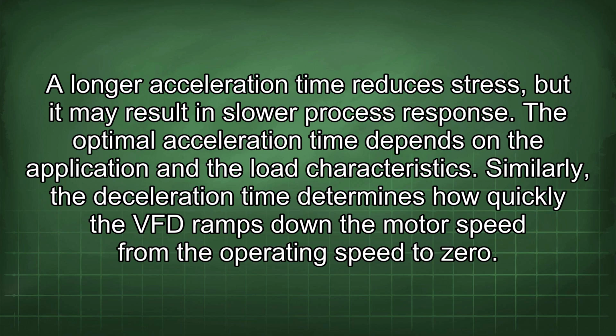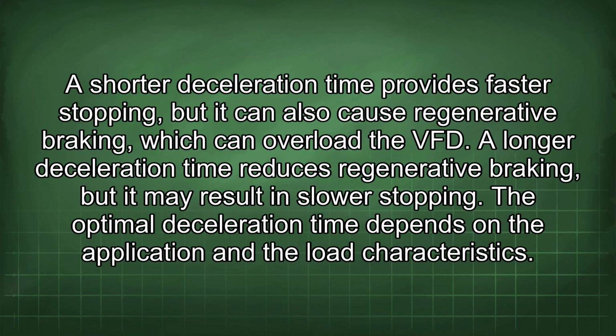Similarly, the deceleration time determines how quickly the VFD ramps down the motor speed from the operating speed to 0. A shorter deceleration time provides faster stopping, but it can also cause regenerative braking, which can overload the VFD. A longer deceleration time reduces regenerative braking, but it may result in slower stopping. The optimal deceleration time depends on the application and the load characteristics.